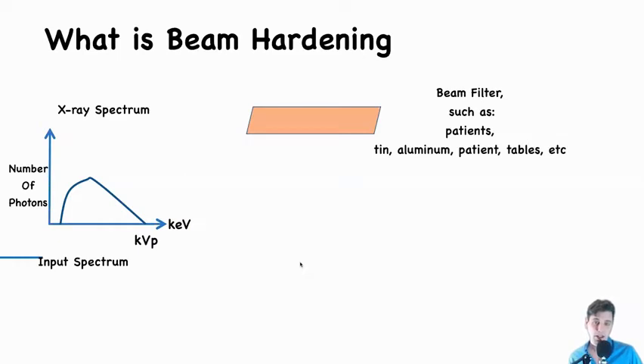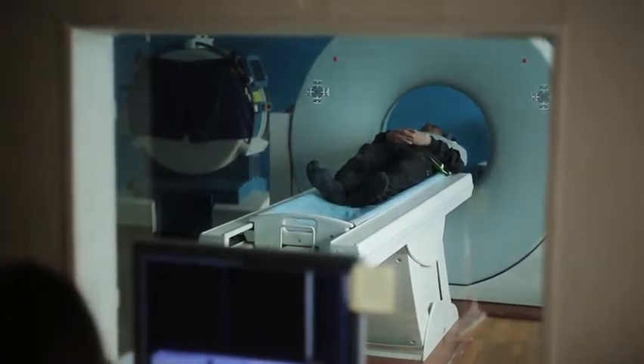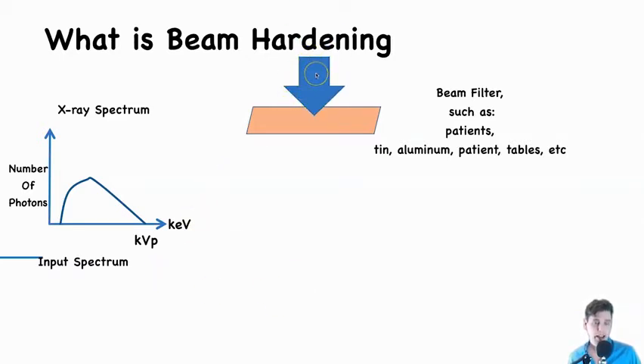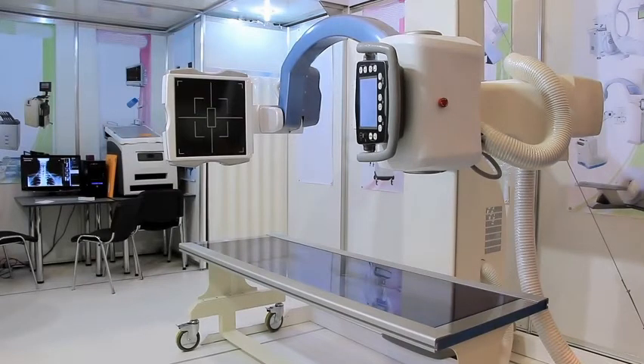What is beam hardening? Beam hardening occurs as x-rays pass through some filter material — that material could be the patient, a table, or the anode itself. X-ray beams produced in medical x-ray tubes are not mono-energetic; they contain many energies, primarily because of the bremsstrahlung interaction.